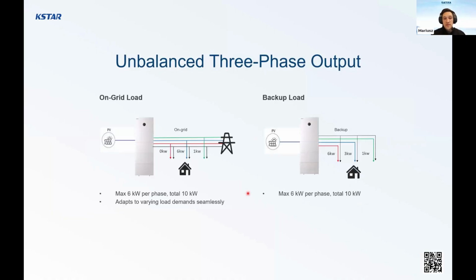Regarding the unbalanced three-phase output, some countries require, for example, if you receive the connection papers from the DSO that you cannot export anything to the grid, you have to be compliant with it on a single phase level. For example, that country is the Czech Republic. And some countries can change this law in the future, so it is better to be prepared in advance. Regarding the output, we can export a maximum of 6 kilowatts per single phase, which is 26 amperes, and for the rest we can export, for example, 0, 1, or 3 kilowatts. It's okay.